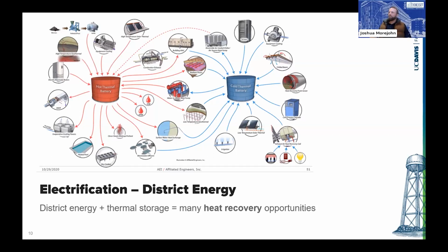There's a lot you can do to both make hot water from different sources, and even raise your chilled water temperature, capturing low grade heat sources with your chilled water. You can run it through a water to water heat pump and produce hot water from that low grade heat source, like our chilled water. So this shows there's a lot of potential, and you can open the door to tapping into that when you have district energy, thermal energy storage, and low temperature hot water instead of steam.